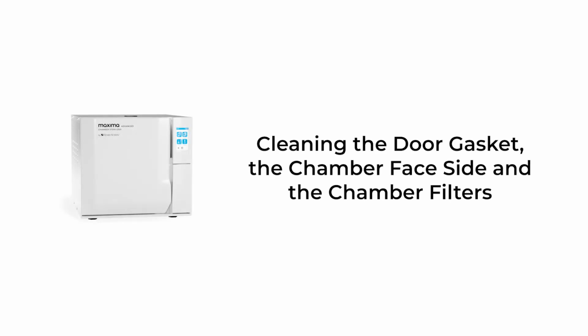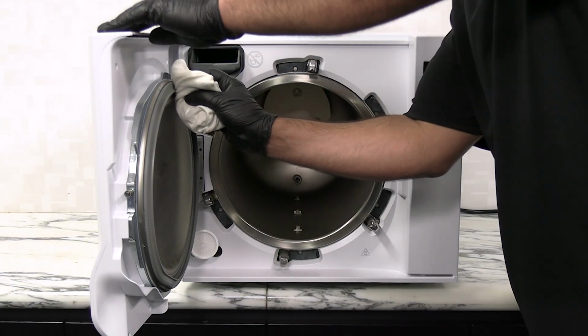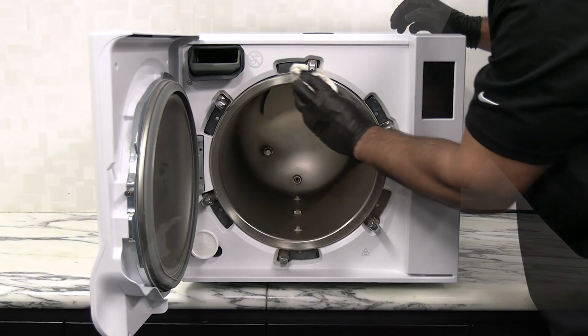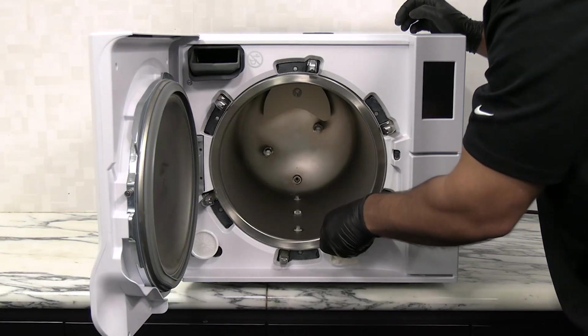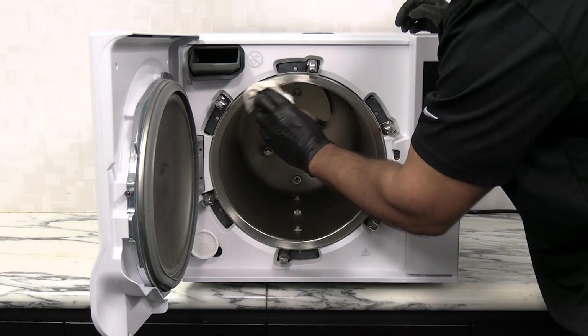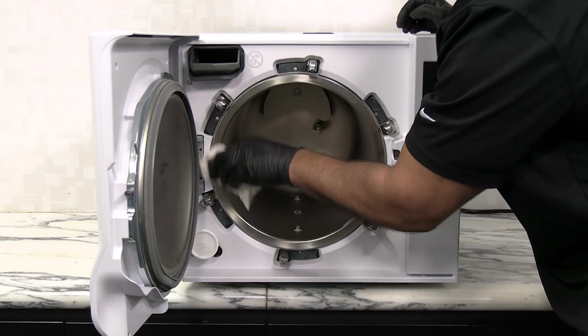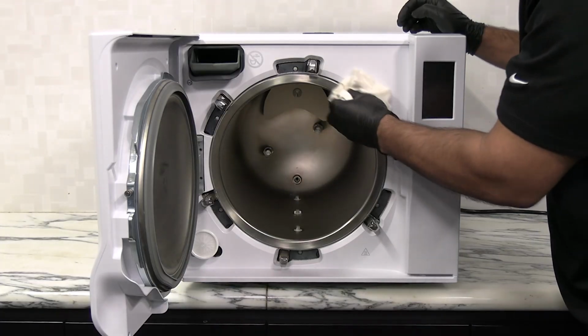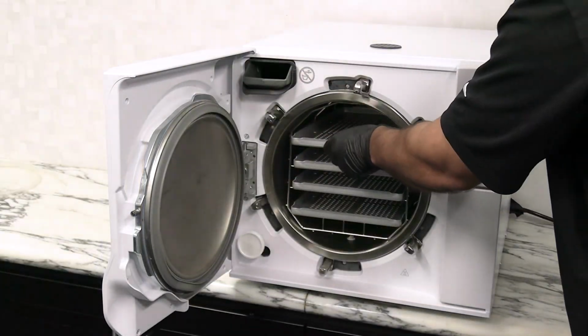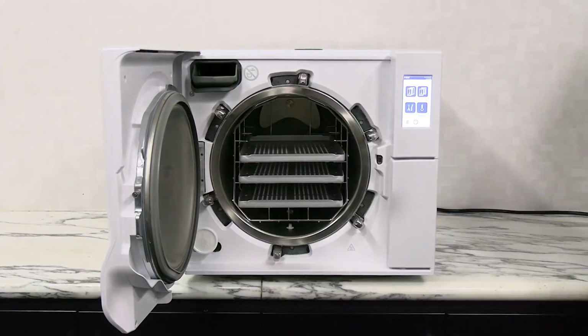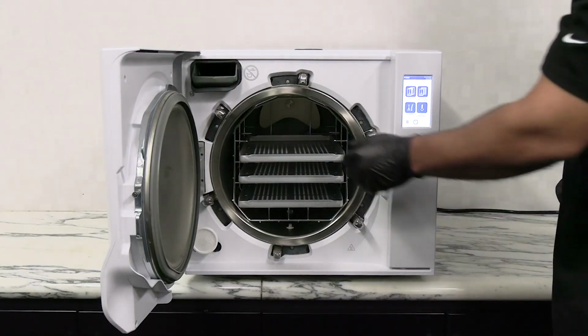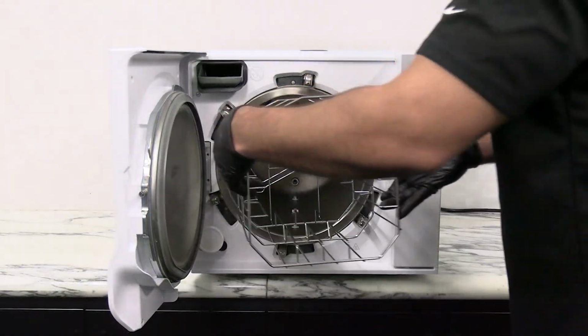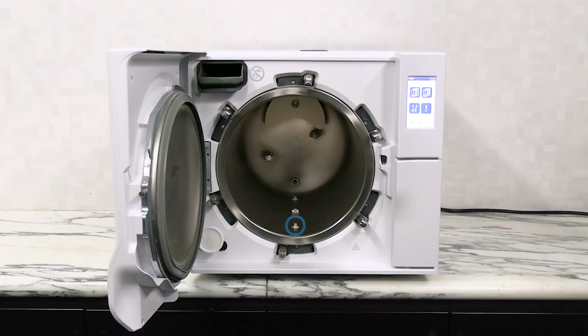Cleaning the door gasket, the chamber face side, and the chamber filters. Clean the door gasket and the outer edge of the chamber with a non-abrasive cloth moistened with clean water. Do not use abrasive products, cutting tools, or sharp objects. Rinse with clean water. Empty the sterilizer chamber by removing the trays and the rack. Remove the filters at the bottom of the chamber by unscrewing them.